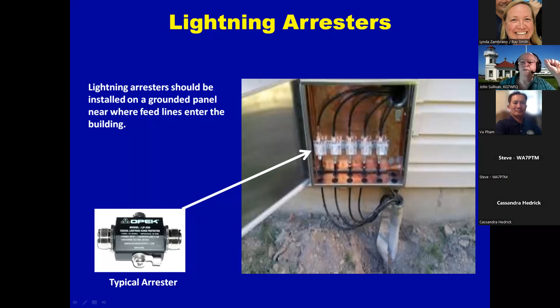You can see here, they've got the lightning arresters connected outside the building, right where the grounding rod presumably is inside that pipe, and it goes straight down to ground - the most direct path possible.